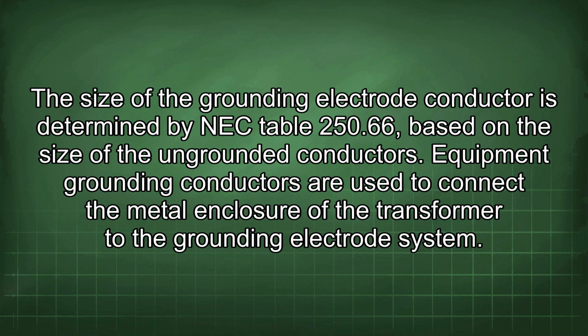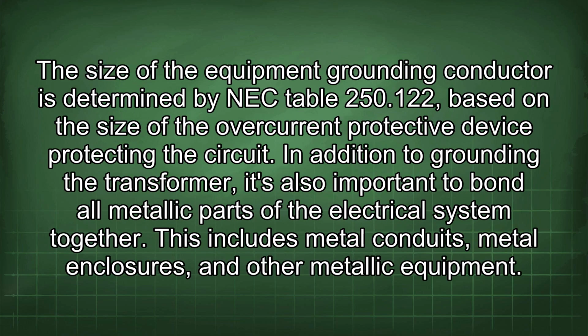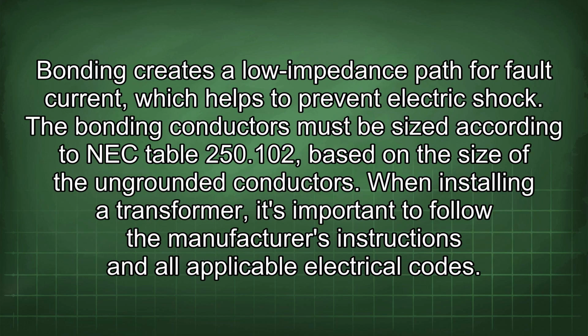Equipment grounding conductors are used to connect the metal enclosure of the transformer to the grounding electrode system. The size of the equipment grounding conductor is determined by NEC Table 250.122, based on the size of the overcurrent protective device protecting the circuit. In addition to grounding the transformer, it is also important to bond all metallic parts of the electrical system together. This includes metal conduits, metal enclosures, and other metallic equipment. Bonding creates a low impedance path for fault current, which helps to prevent electric shock. The bonding conductors must be sized according to NEC Table 250.102, based on the size of the ungrounded conductors.